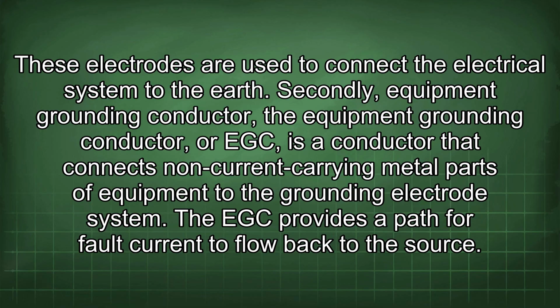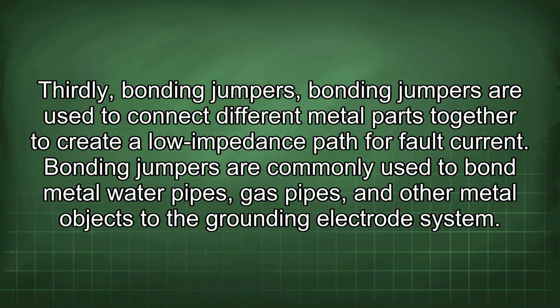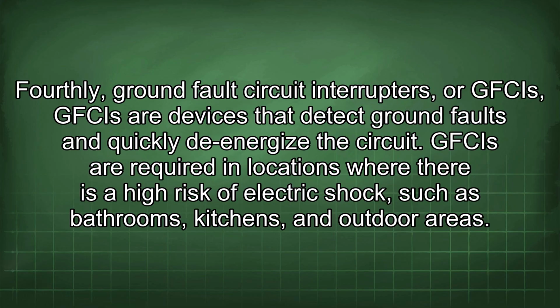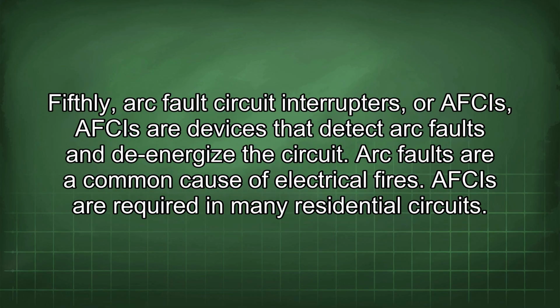The EGC provides a path for fault current to flow back to the source. Thirdly, bonding jumpers. Bonding jumpers are used to connect different metal parts together to create a low impedance path for fault current. Bonding jumpers are commonly used to bond metal water pipes, gas pipes, and other metal objects to the grounding electrode system. Fourthly, ground fault circuit interrupters, or GFCIs. GFCIs are devices that detect ground faults and quickly de-energize the circuit. GFCIs are required in locations where there is a high risk of electric shock, such as bathrooms, kitchens, and outdoor areas. Fifthly, arc fault circuit interrupters, or AFCIs.